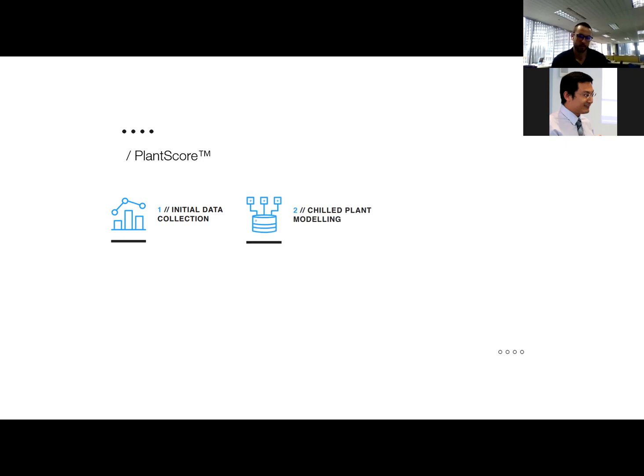So that's the next step there, the chill plant modeling. We've got a bunch of algorithms which take this data and calculate, as we'll see, COP as a function of lift and part load of a chiller, and also look at the pumps and cooling towers which serve those chillers, to get a central plant model that represents mathematically what's happening in the plant currently. So we'll bring all that together into a single central plant model.